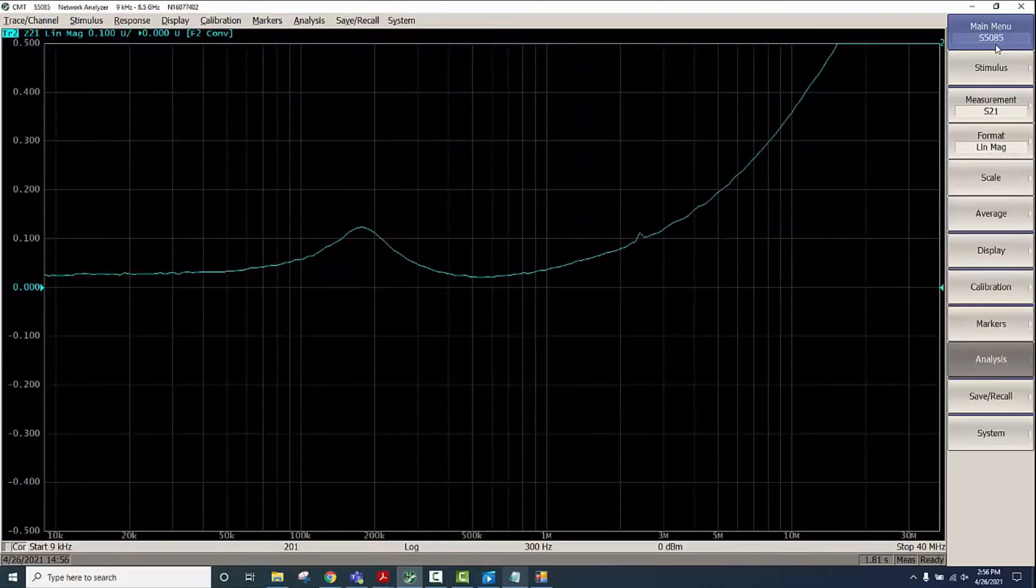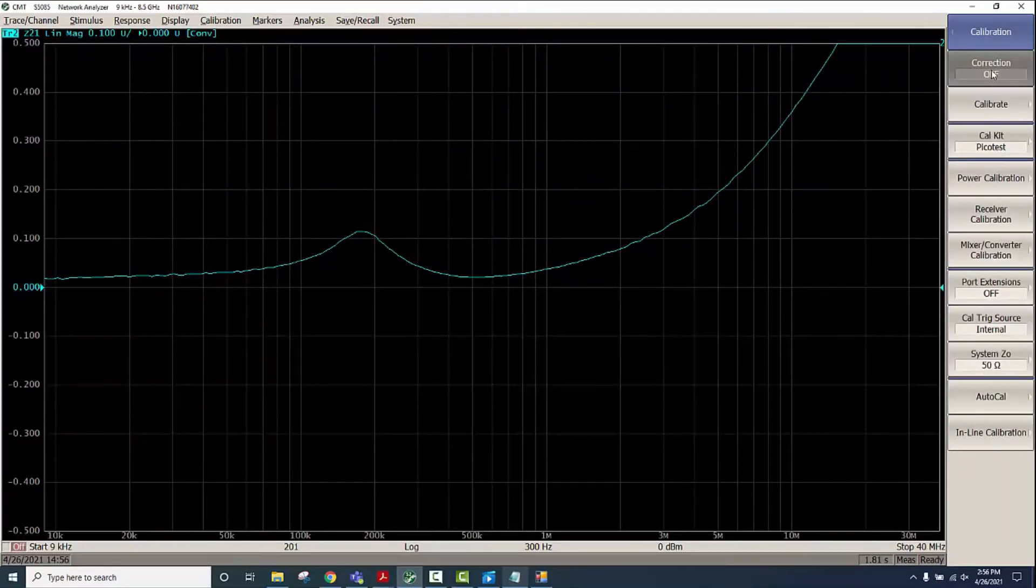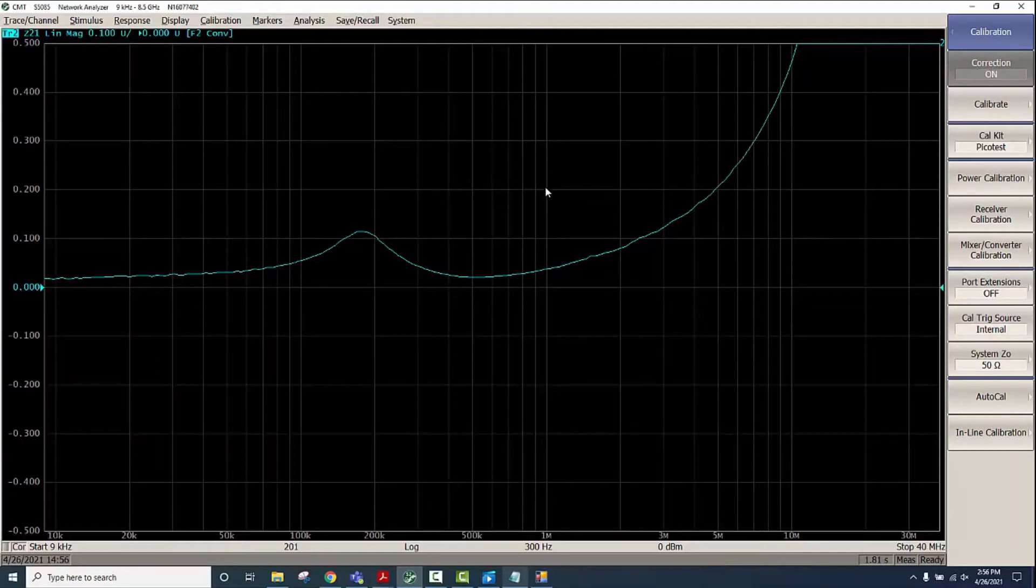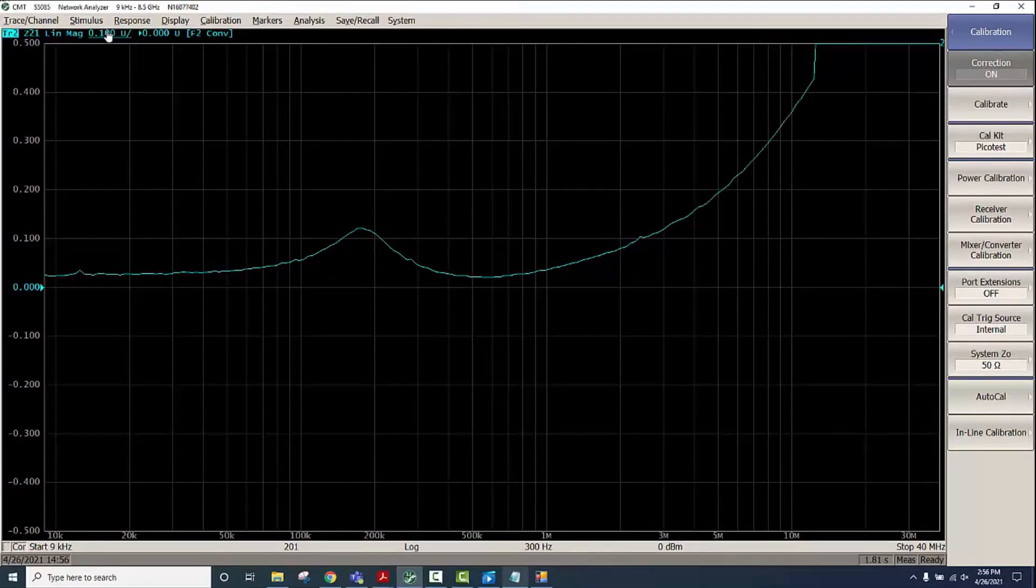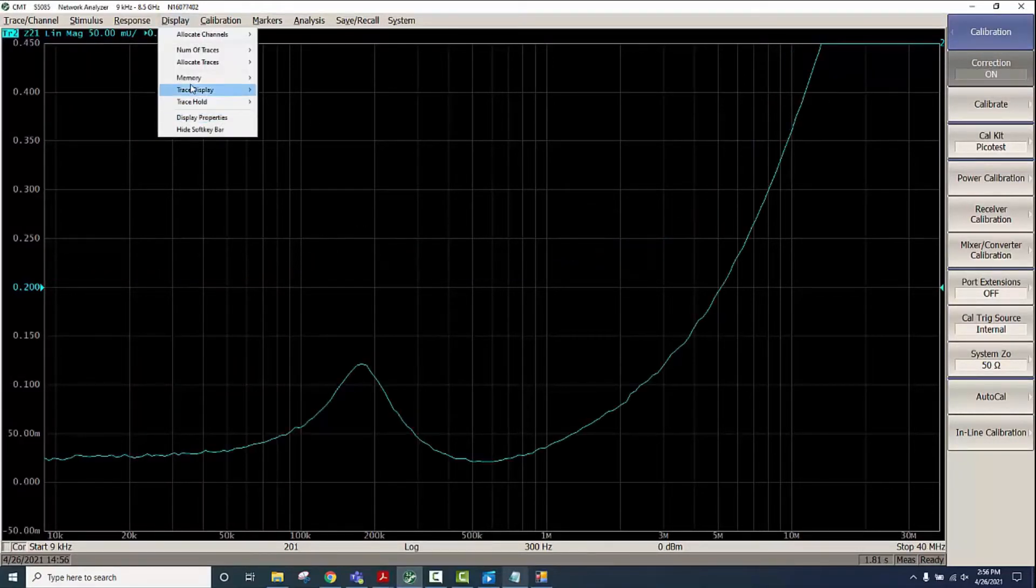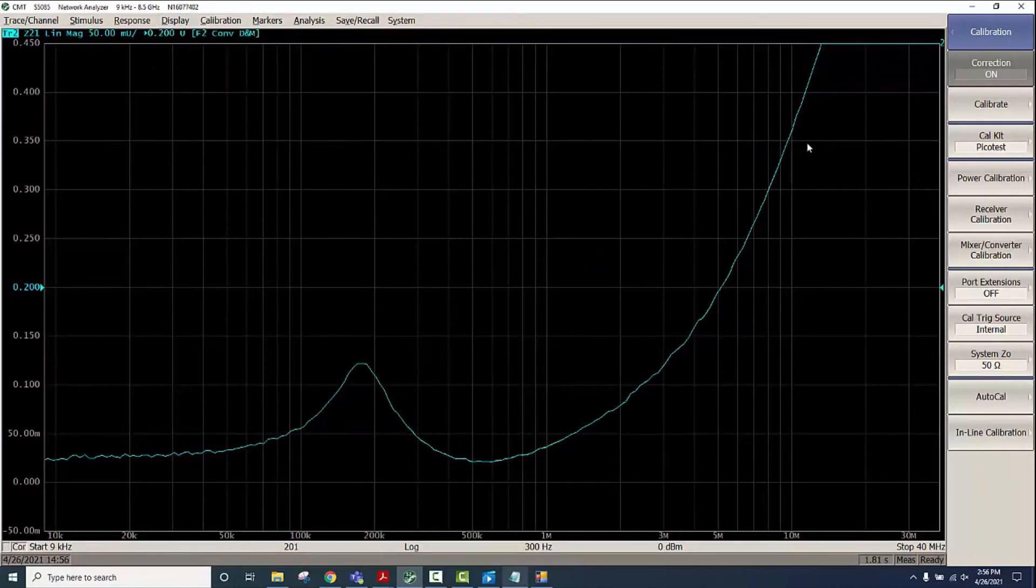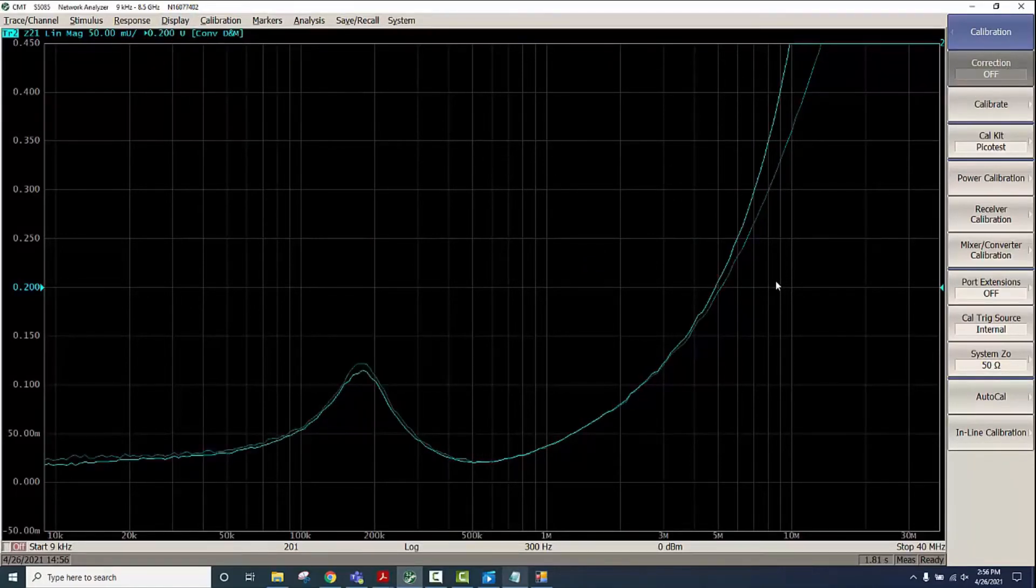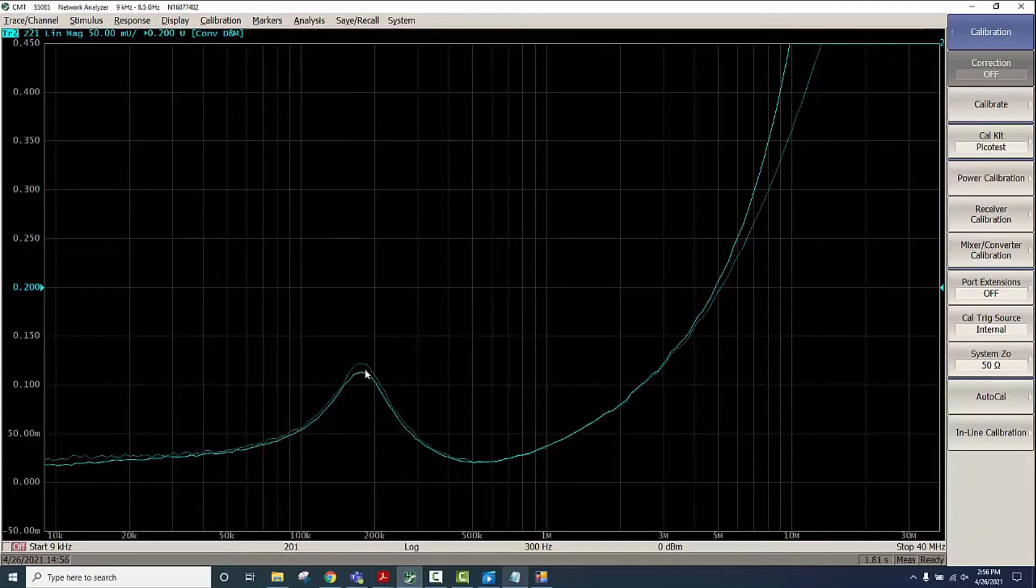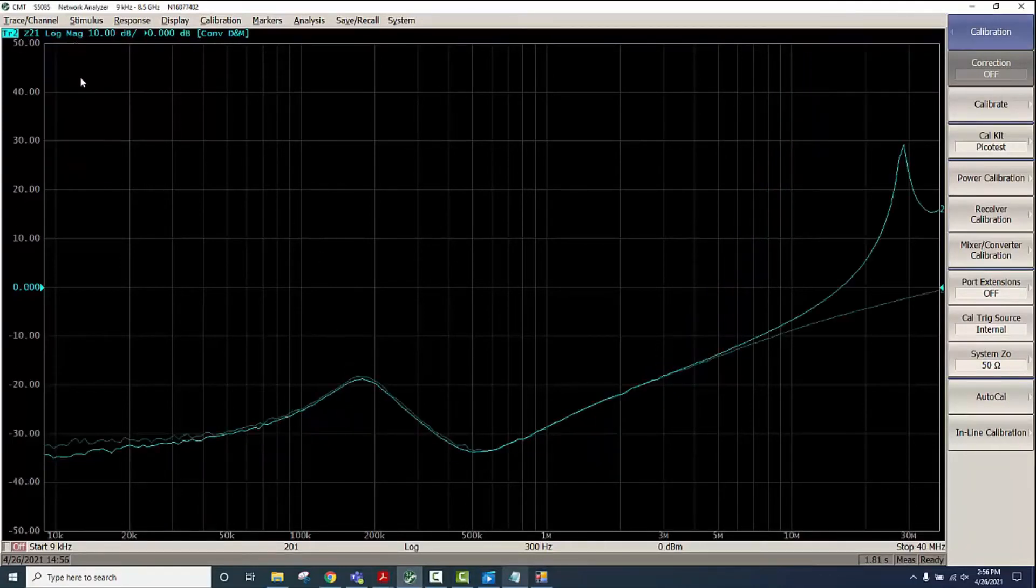We can also look at the measurements with and without calibration. This is with correction on so we'll put this to memory to compare and then we'll do correction off. You can see there is some small difference there. We can also zoom in and see how the measurements would look like in either the log scale or the linear scale.